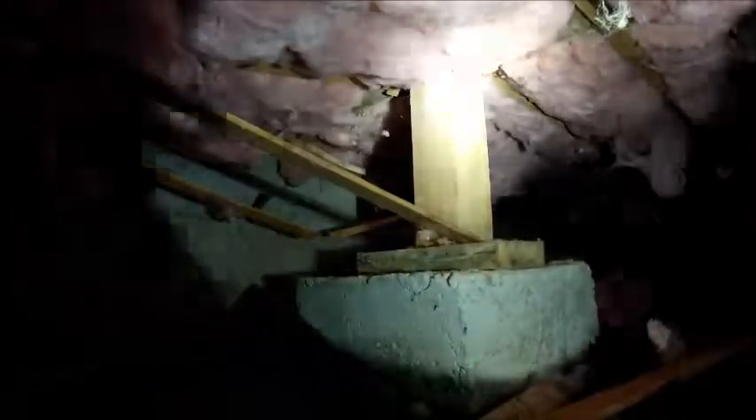This is the hot tub wire, and as you can see it's going up and through the pool area. This wire was never tacked up to the floor. There's a bunch of wiring over there — those are falling. And fallen insulation into the puddle. Broken strips that were holding up the insulation.